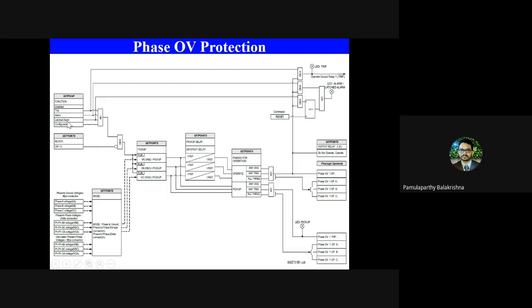Latched alarm means there is an alarm condition in the field, but the alarm can come when there is an overvoltage, and that overvoltage will go after some time. The moment this overvoltage goes off, this alarm will become off. In order to avoid that condition, another term called latched alarm is introduced, where until the operator sees that some alarm has come and acknowledges it, the alarm will not go. Otherwise, there will be an overvoltage condition, voltage will cross, alarm will come, but the moment voltage becomes normal, the alarm will disappear. So the operator will never know that there was an overvoltage alarm. That's why latched alarm has been introduced, where unless the operator acknowledges that he has seen the alarm, it will not go.